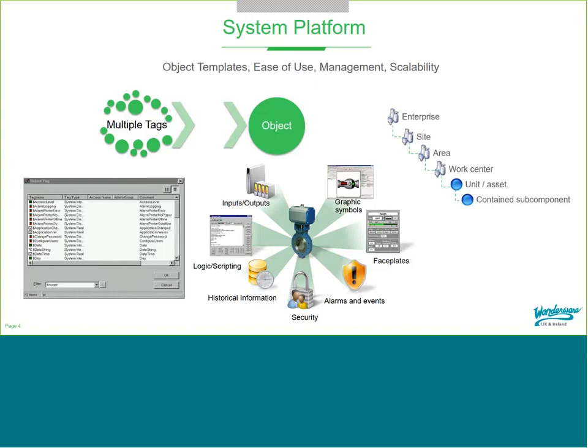System Platform also organizes the system into a plant model. So the plant model is, again, a virtual representation of essentially the physical layout of your facility. So if you start at an enterprise layer, perhaps go down to site, so that's the site name, then onto an area which is a particular region, and then perhaps a work center like a line, and then we're actually putting our assets under those line names. The point behind this is that you can understand the physical location of where things reside because you walk around your facility on a regular basis.